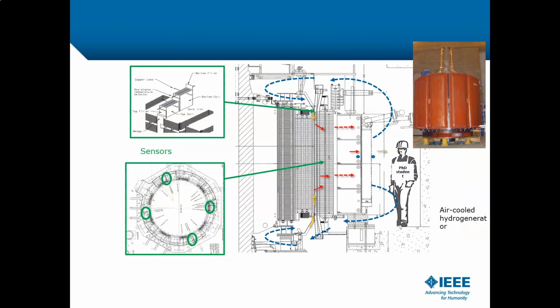Let's look at the cooling system in such a machine. Here we can look into the machine from the side, and we have the heat exchanger here, and we have cooling air, the blue one coming out, cold air, that is drawn over the windings. This is the stator bar. Here is the rotor, and this is the air gap where you can see the yellow here. The cold air is drawn over here through the fan, down into the air gap and through the stator, and it's then heated as it goes through the ducts and out to the heat exchanger.